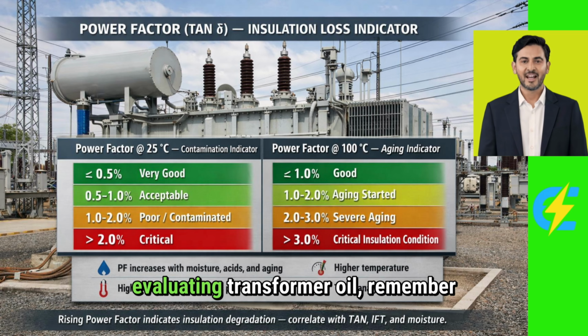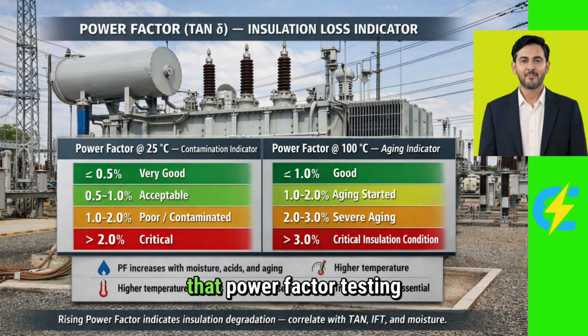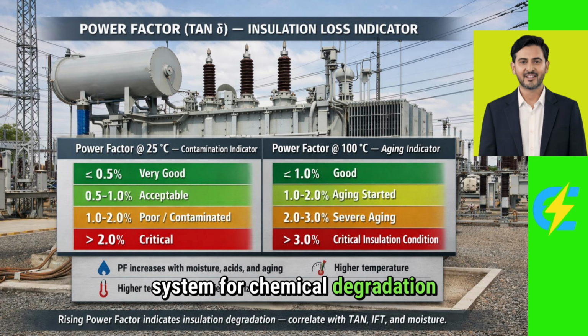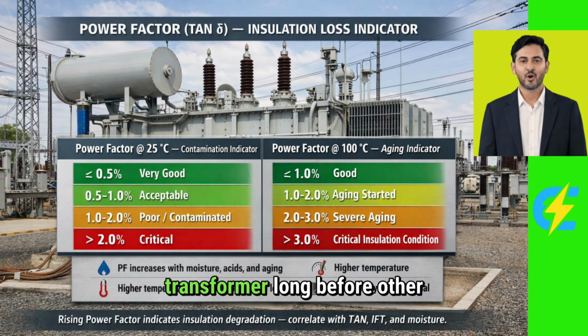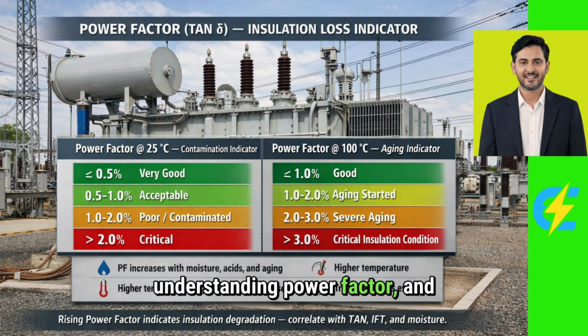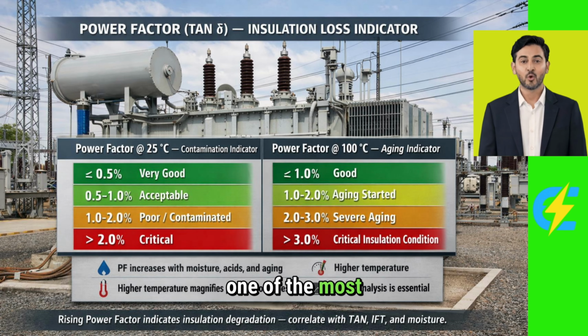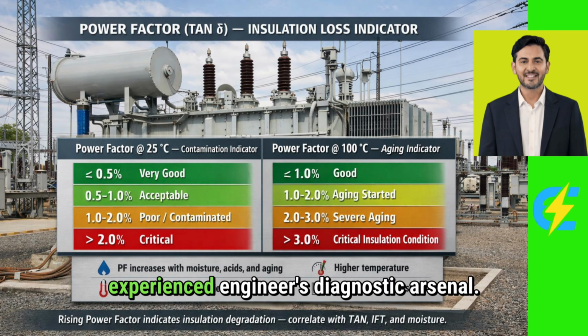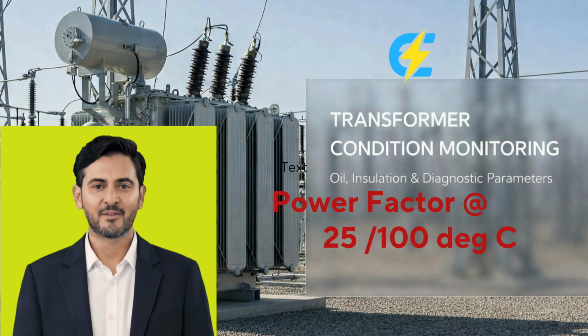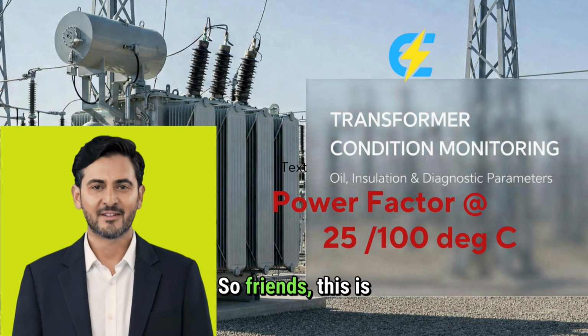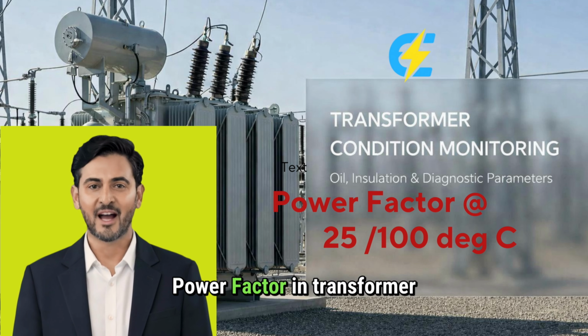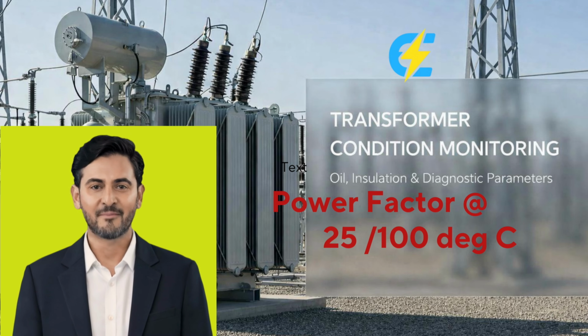The next time you're evaluating transformer oil, remember that power factor testing at both 25 and 100 degrees Celsius is not just another test to check off your list. It's your early warning system for chemical degradation that could compromise your transformer long before other tests show problems. That's the power of understanding power factor, and that's why it remains one of the most valuable tools in an experienced engineer's diagnostic arsenal. So friends, this is the real meaning of power factor in transformer insulation.